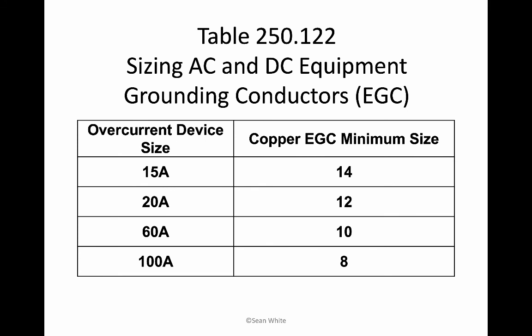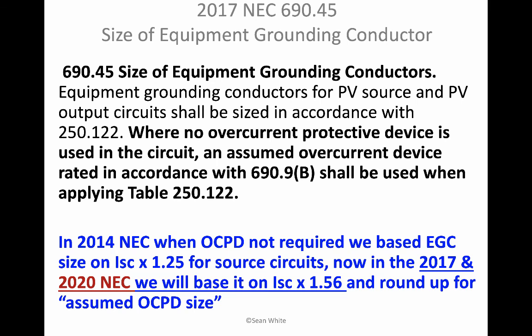Another thing is you don't use 1.56 if you're using DC to DC converters. And what's the other name for a DC to DC converter? What do you call it? Optimizer, if you're optimistic. And if you don't have an overcurrent protection device for the 2020 National Electrical Code and the 2017 National Electrical Code, then you would base the assumed overcurrent protection device size on short circuit current times 1.56, and that is for PV source circuits and PV output circuits.